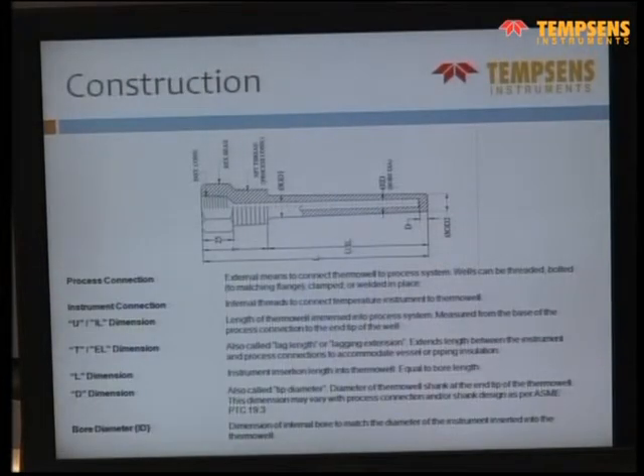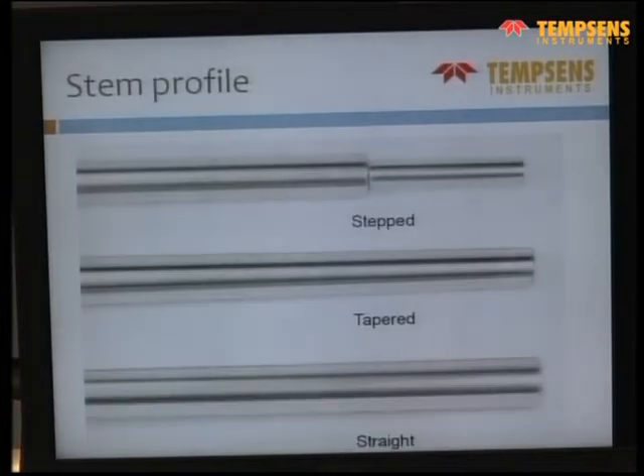Is the smaller diameter the sensing side, or does taper mean larger diameter, small diameter? No, you can see the taper portion is at the measuring side. All thermocouples or RTDs measure their own temperature, so if you have a larger mass, it will take more time to heat up or cool down. So the taper portion is always at the bottom, which is the sensing, hot end. This is more in terms of RTD.